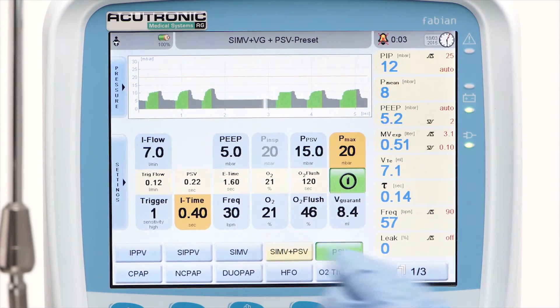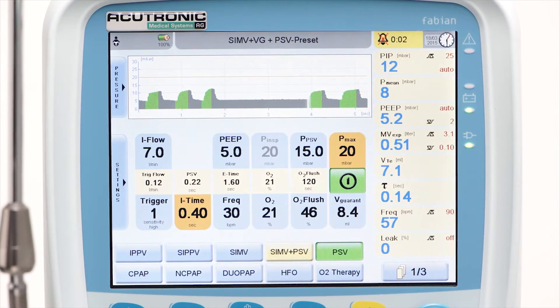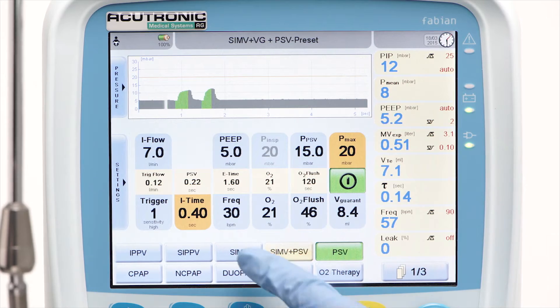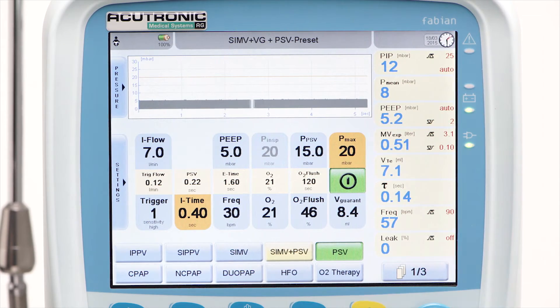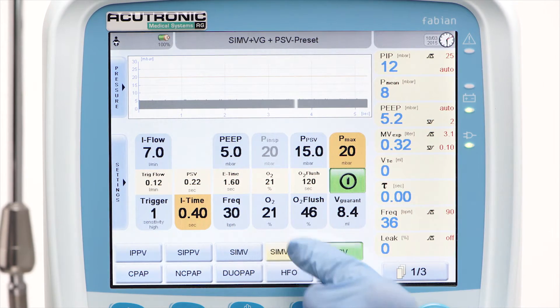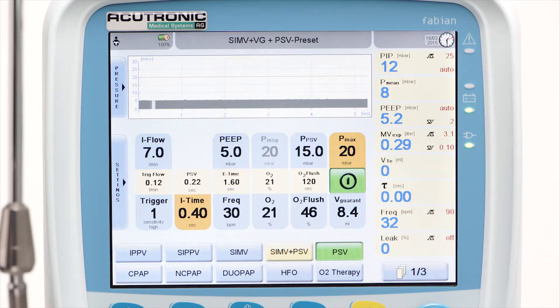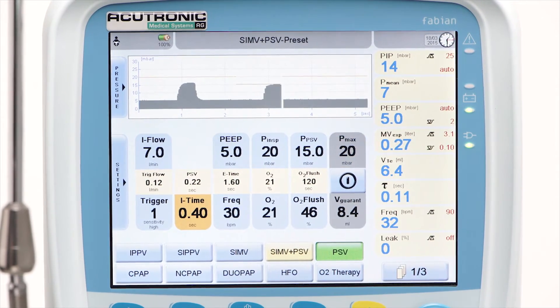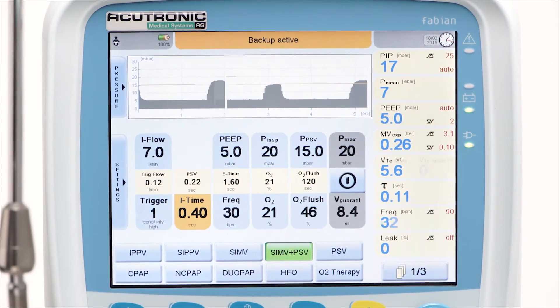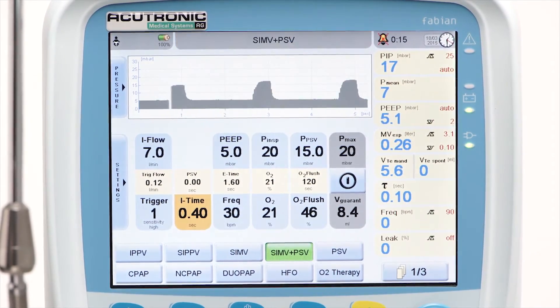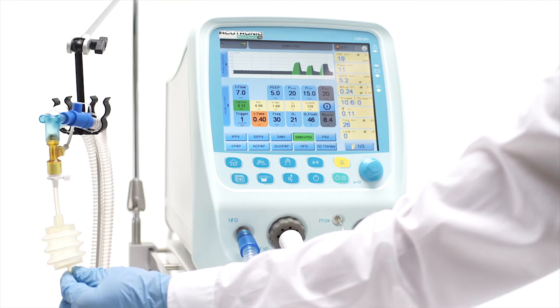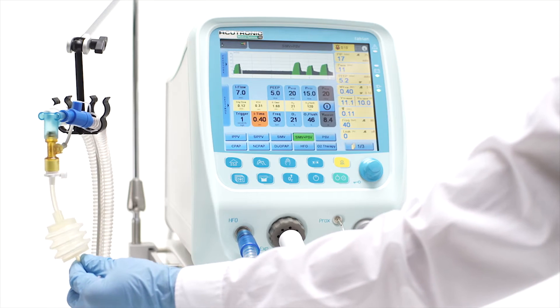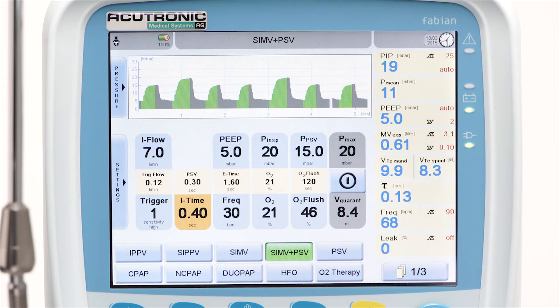SIMV plus PSV mode is a combined mode of ventilation which allows the patient to trigger time-cycled, pressure-limited strokes like an SIMV mode for a preset amount per minute. In addition, between the SIMV strokes, the patient's spontaneous breaths are also assisted with a preset pressure support level Ppsv, with a flow-cycled breath.